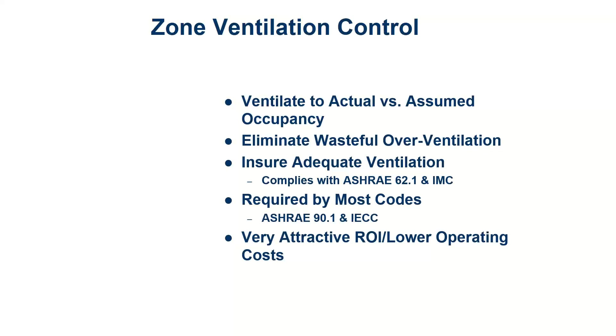You don't have to worry about its ability to keep heating and cooling, because whenever you do DCV, you always design the mechanical equipment to handle the peak day, which is the most amount of ventilation, assuming everybody's there. If they're not there, you throttle it back. So if for COVID you want to bump your CO2 set point higher, it'll allow your damper to open more, but not more than what would have been the code amount - just more than what you would have had on a partially occupied day. All right, let's see if we have any other questions that need to be addressed.